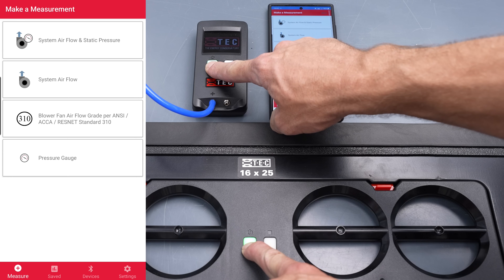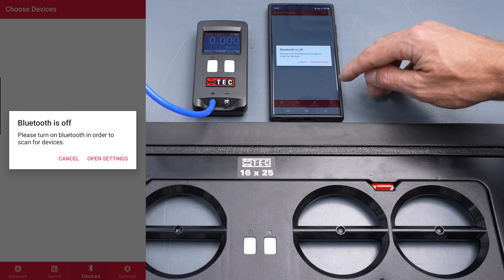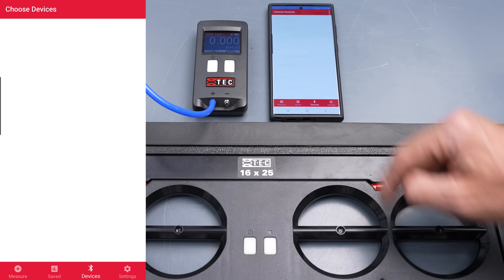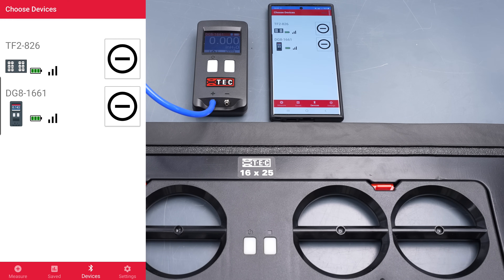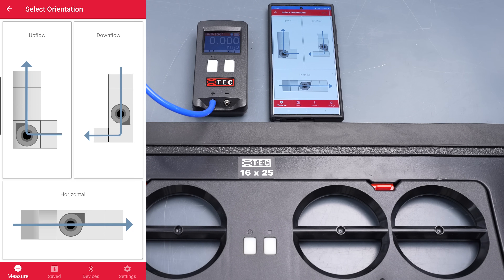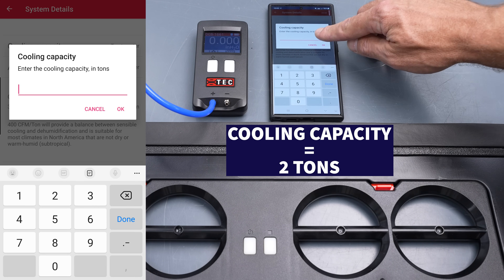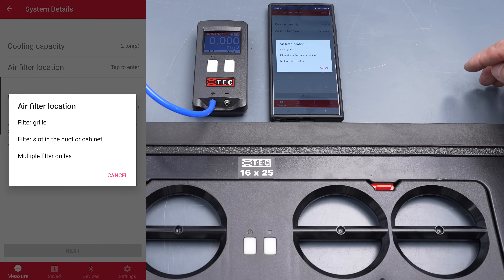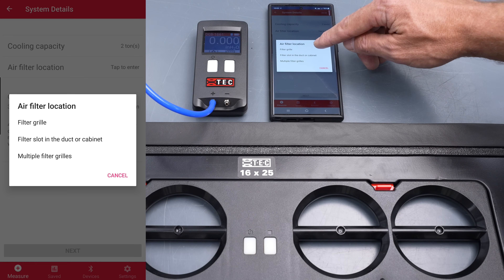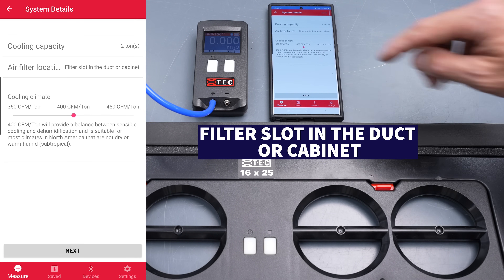You want to make sure that you have the TrueFlow app — it's a free app — downloaded on your phone or tablet. You're going to turn both devices on. These are Bluetooth, and we're going to be using our system airflow, which is workflow number two. First we want to go to Devices, open our settings, make sure that we have Bluetooth on. We're going to open our system, add both devices, and then go back to Measure. Click on system airflow — this is a furnace and air conditioning system so we'll select that. We'll select upflow. The cooling capacity in BTUs on the outdoor unit is two tons, so we just select two. Our air filter location is in the filter slot in the duct or cabinet.